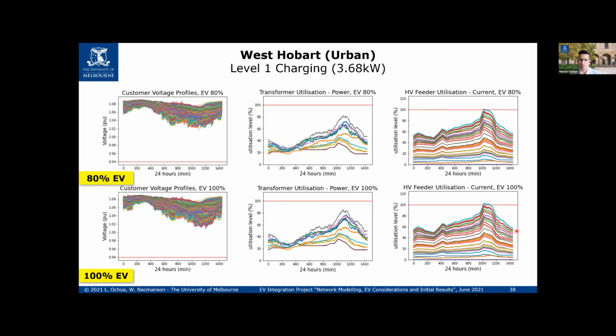If we continue, voltage is still fine, transformers are okay, and it's really the high voltage feeder conductor that is carrying the aggregated power and currents. It gets exceeded to a little bit more than 100%, which is really negligible, to be honest, because our conductors and assets in general can actually be overloaded for a few hours.